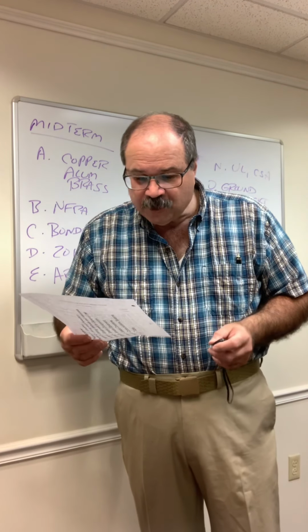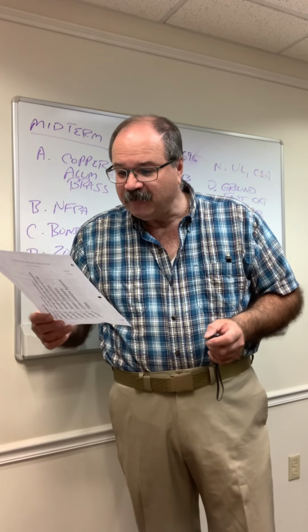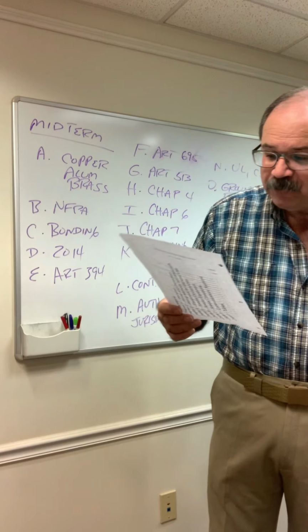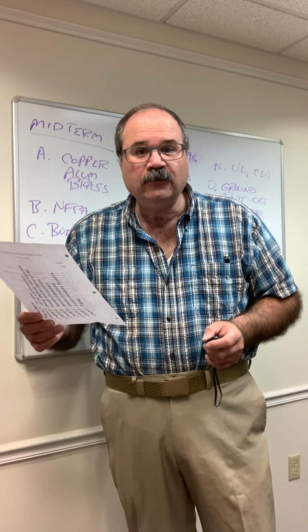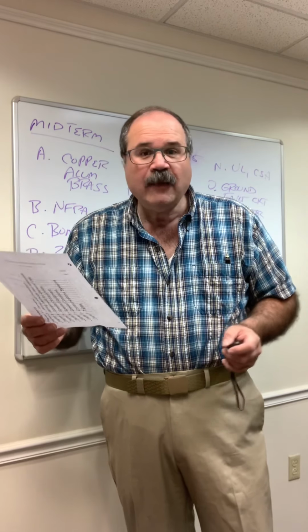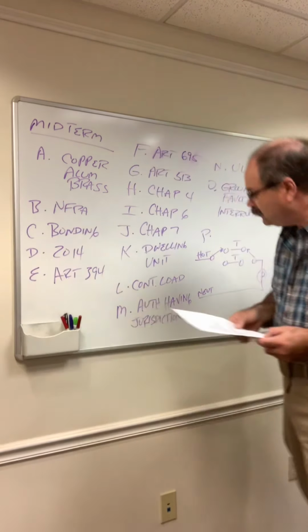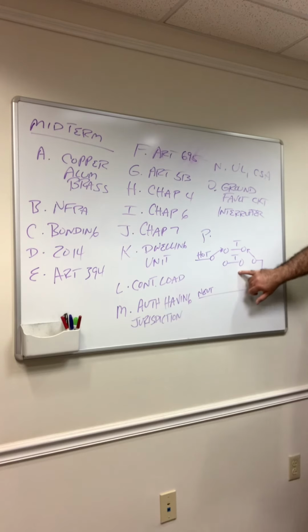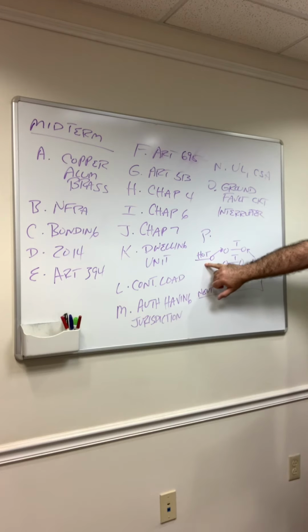And lastly, question P, I wanted you to draw the wiring diagram for 2 3-way switches supplied by a 120 volt branch circuit, feeding a 120 volt incandescent lamp, and label each of the conductors. For the switching arrangement, I have the first 3-way here, the second 3-way here, and the common where I have the hot conductor applied. The code refers to this as the ungrounded conductor.